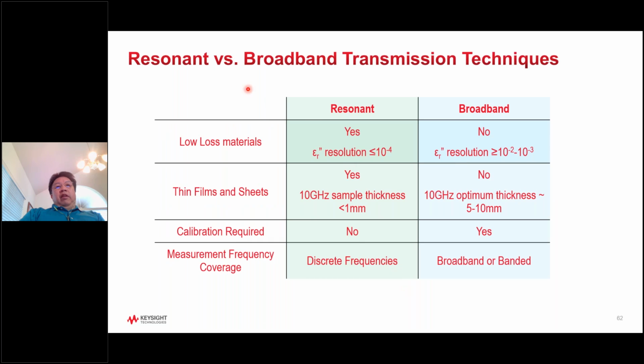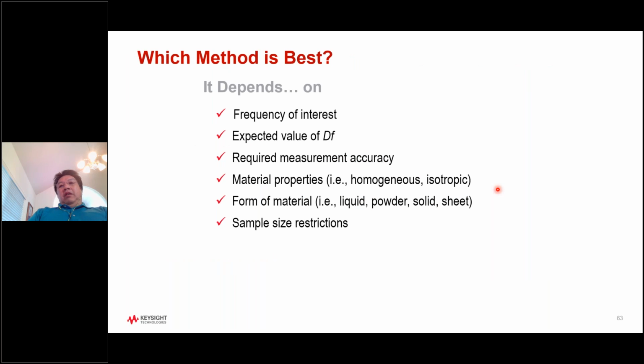So in terms of overall resonant cavity versus broadband, because most of the time people want to measure multiple frequency points, they don't want to buy many fixtures. So in comparison, for low loss, with the resonant cavity we can measure down to 10 to the minus 4 in terms of measurement resolution for the DF or the imaginary part. Okay, but of course, for different thickness and frequency, you require a different fixture. For the broadband, the measurement resolution is less, but you can measure multiple frequency points because you just sweep frequency. Okay. So I covered 4 or 5 major measurement methods available from Keysight.